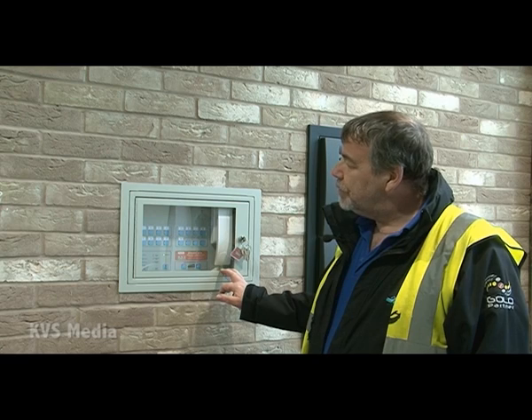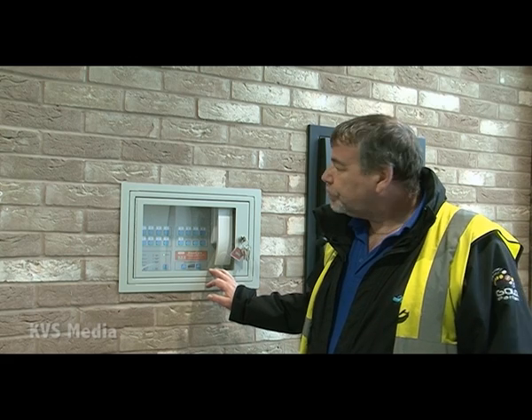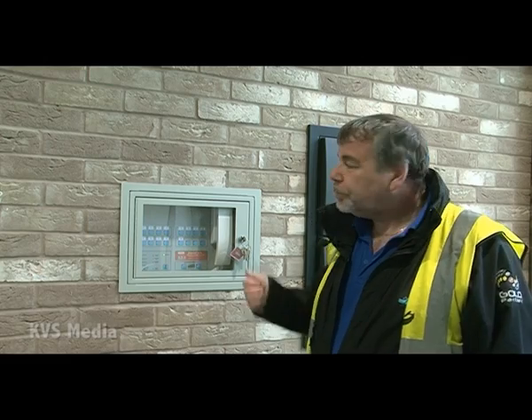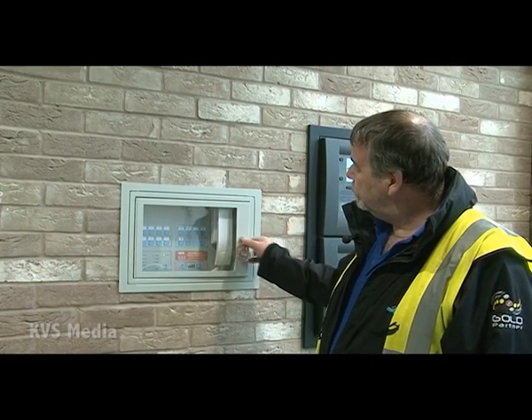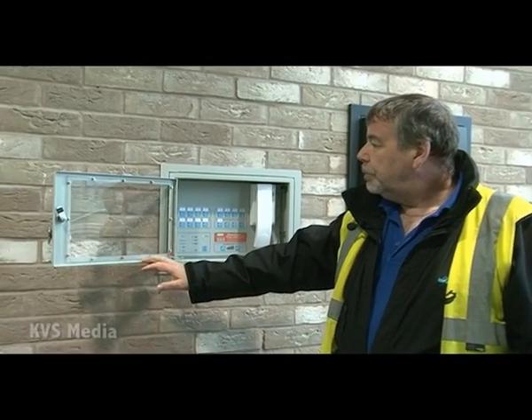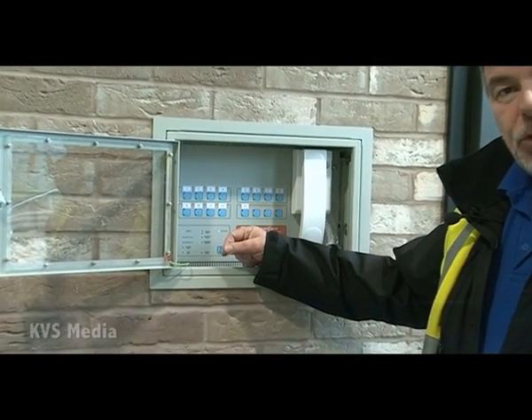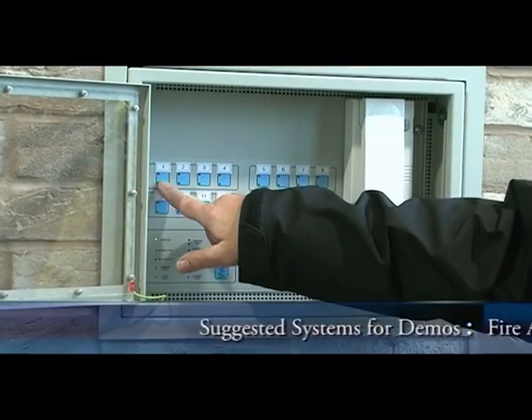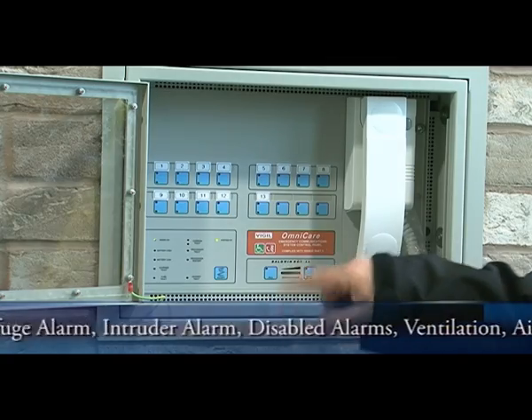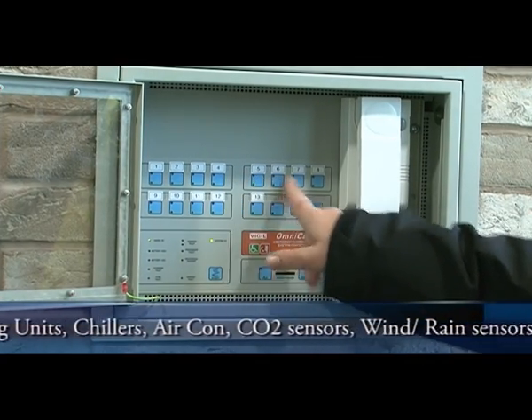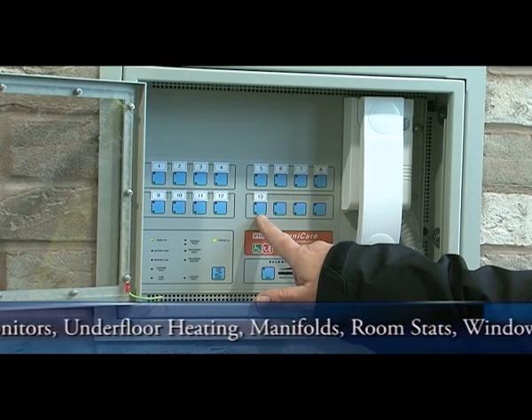When you're not in a fire condition and you were to press a button on the stairwell unit, it would say system in standby, which is to allow the system not to be interfered with by students. So just to reiterate, the use of the disabled refuge call alarm system is only available during a fire condition. And if I just open the panel up, the 4 disabled refuge alarm points are associated with indicators 1 through to 4. The other buttons 5 through to 13 are associated with the disabled toilet alarms.